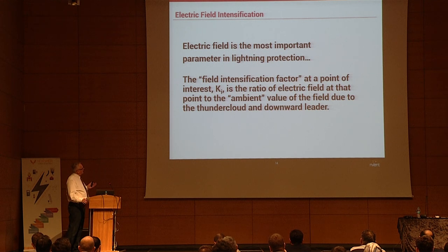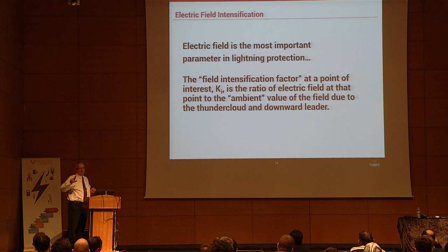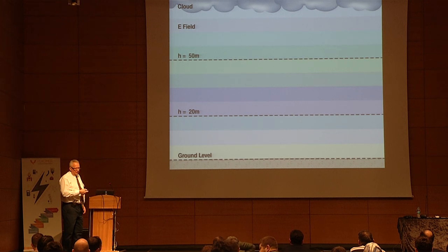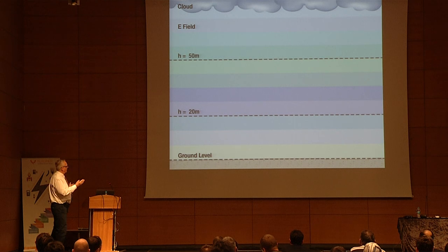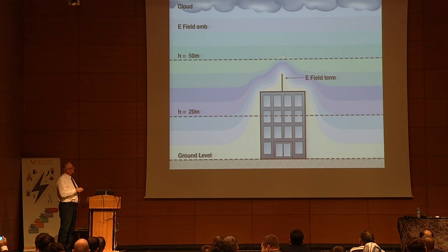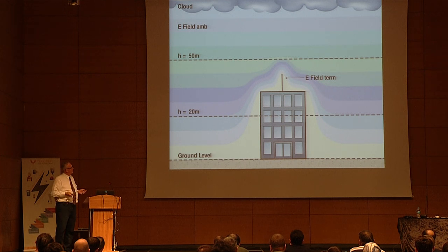Electric field is the most important parameter in lightning protection. The field intensification factor Ki is the ratio of the electric field at the point of interest to the ambient value due to the thundercloud and the downward leader. In a green field with no structures, field lines are uniform. But when you put a structure with a lightning terminal there, the field lines get compressed — the electric field is intensified by bringing the field lines closer together.